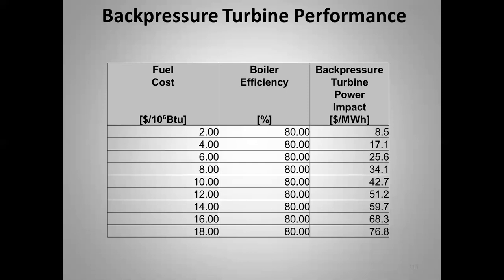At $2/MMBTU, the cost is $8.50 per megawatt-hour — that's only $0.0085 per kilowatt-hour, less than one penny. A plant might pay 6 cents per kWh, or $60 per MWh. So with good fuel prices, there's a strong economic case for generating your own electricity — that's what this analysis is about.